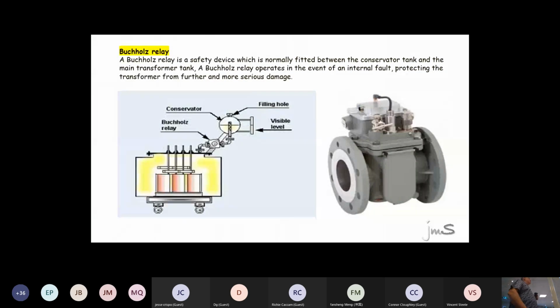Right. Oil moves through a transformer. And if the oil gets contaminated by air inside that, there's a special relay called the Buchholz relay. This Buchholz relay will detect any types of air bubbles inside oil. So think about this. You all agree that bubbles will always rise up. Right. So if the oil flows through that valve or that big relay, the oil will go up and activate micro switches. Normally the micro switches inside there in the olden days used to be mercury switches. Now as the bubbles go through it, it will bump the switches up, and when it starts bumping it, the micro switches will activate an alarm or even switch the transformer off.